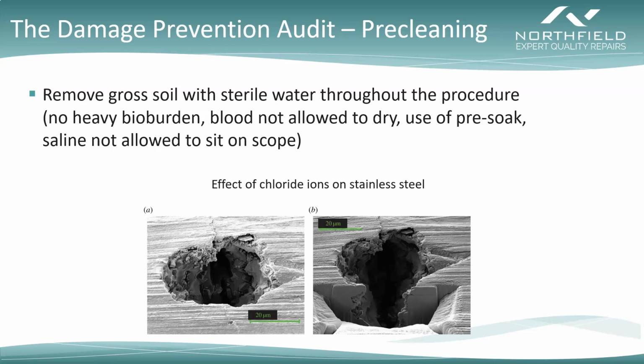Now, keep in mind that stainless steel, while it is very strong, has one critical weakness, and that critical weakness is the effect of chloride ions that are present in particularly saline, but are also present in blood as well. And those chloride ions will eat the protective layer of chromium oxide that sits on top of those stainless steel sheaths. It will also do a lot of damage to the glass on the lenses as well. So really want to make sure that both blood and saline are not allowed to sit on the scope for long periods of time. It will do a lot of damage.